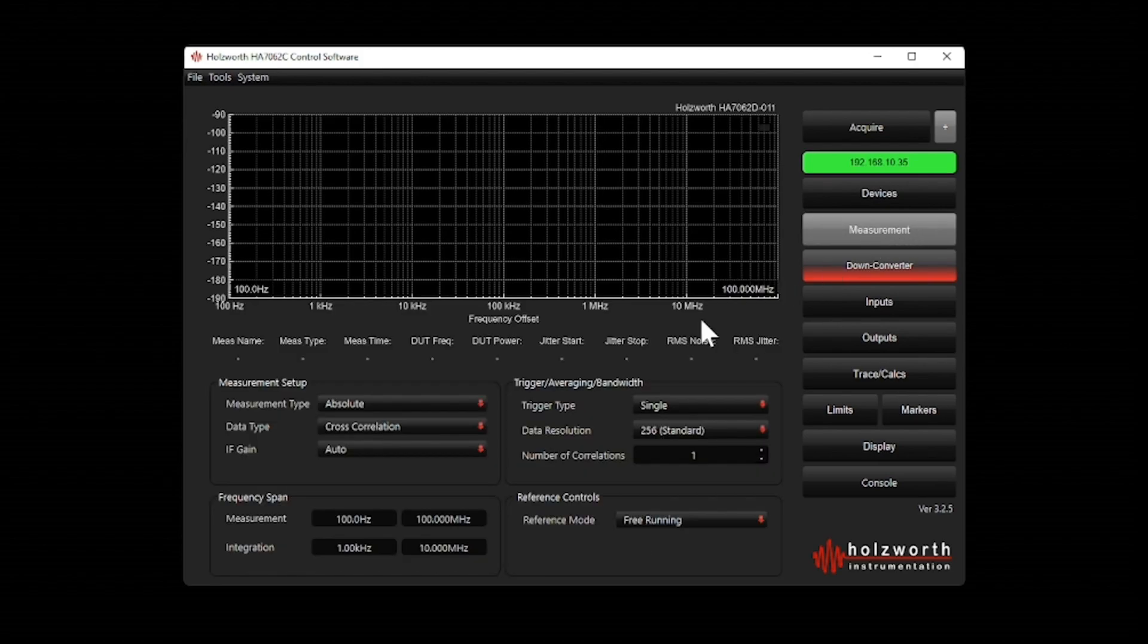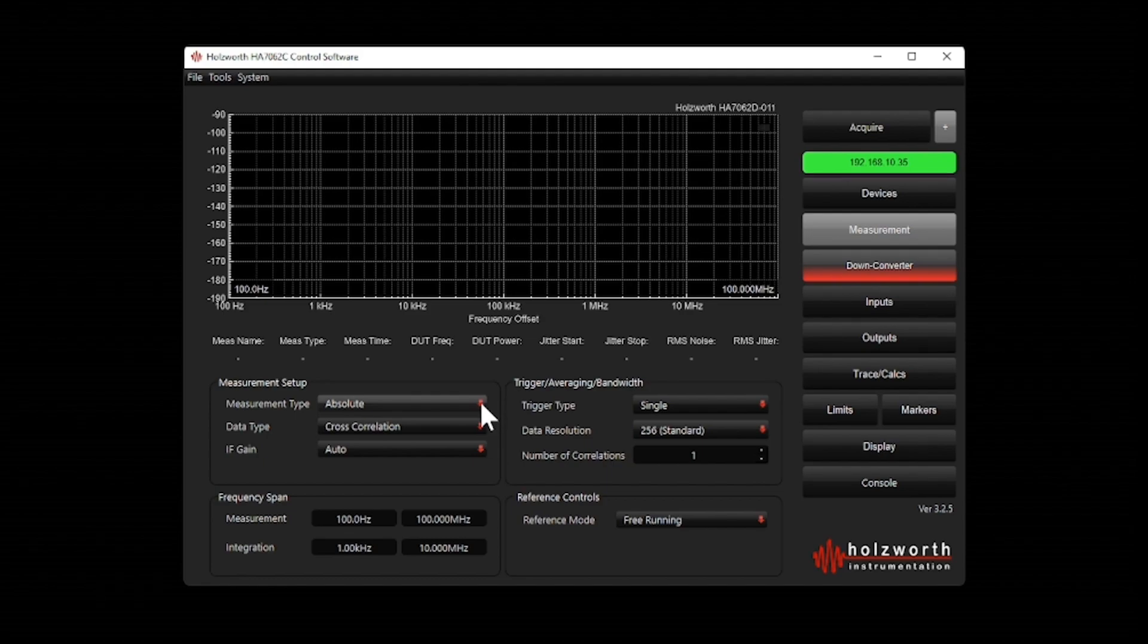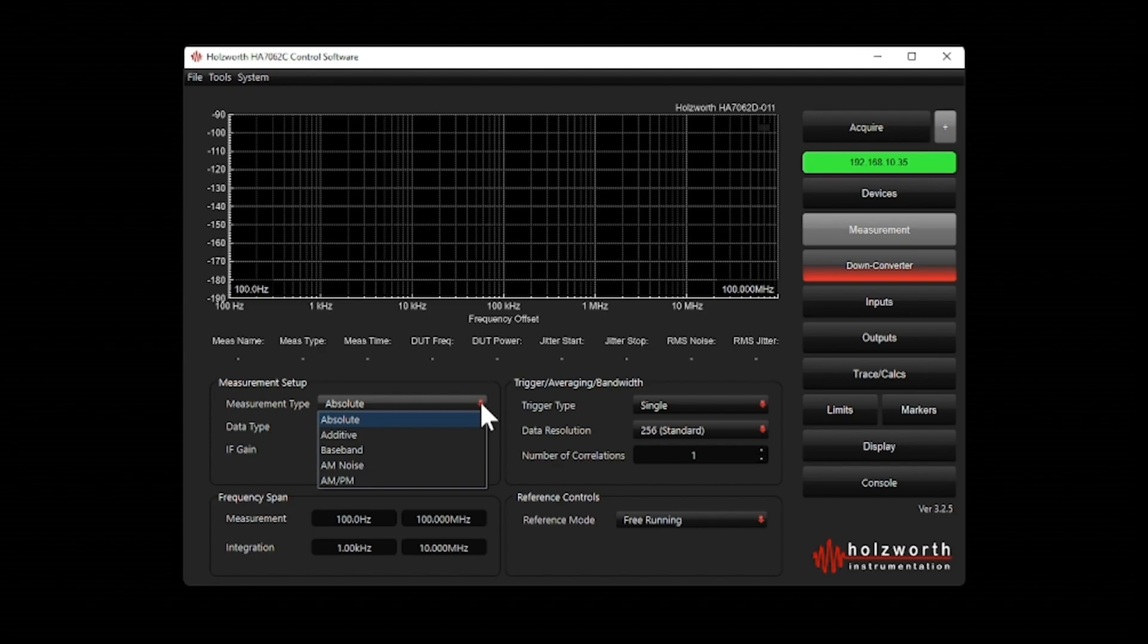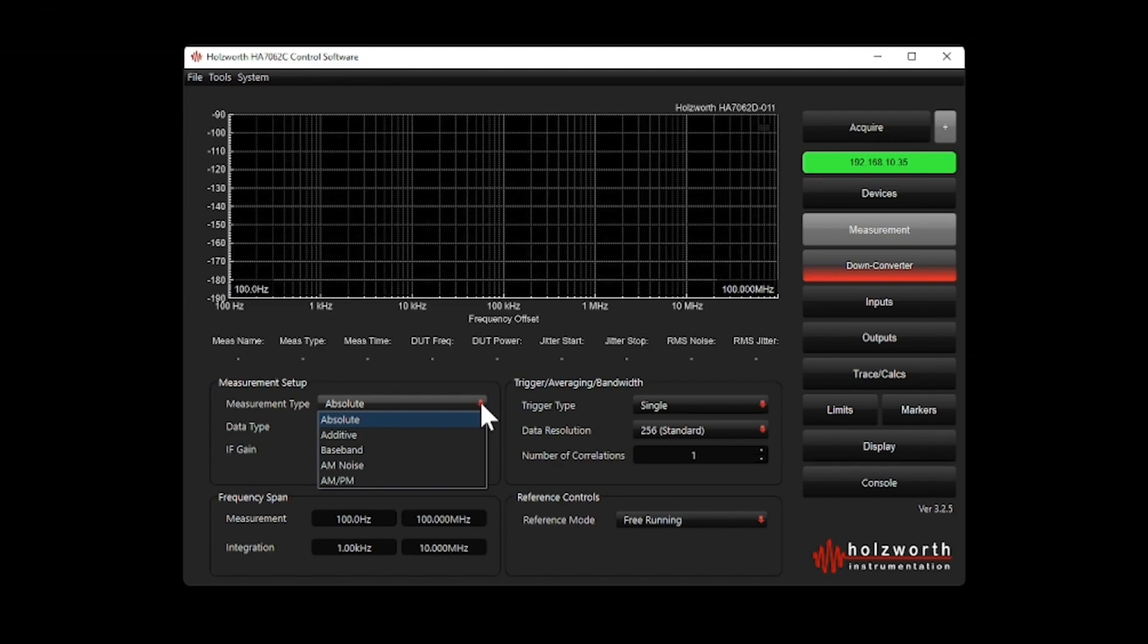The next thing I want to do is set up the type of measurement I want to make. I want to make an absolute phase noise measurement, but you can see I have a number of other options to choose from: additive phase noise, baseband, amplitude noise, and AM-PM.